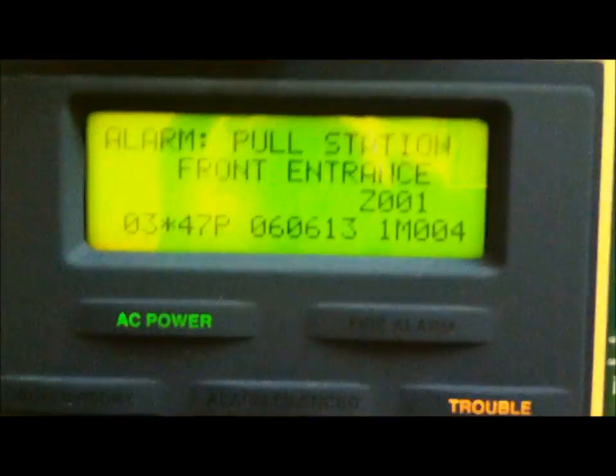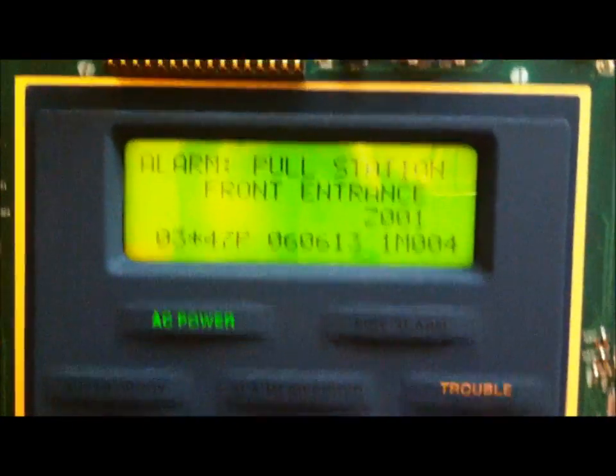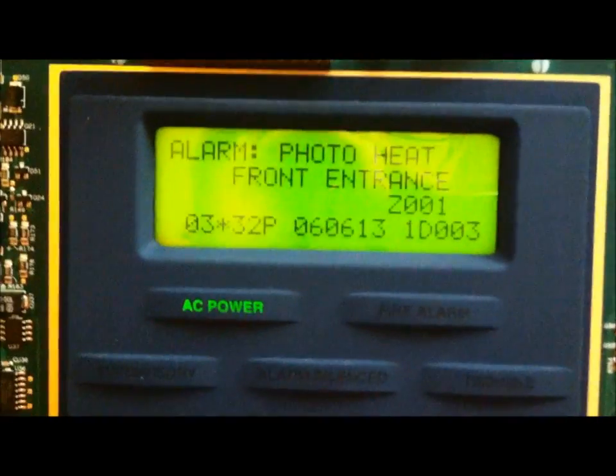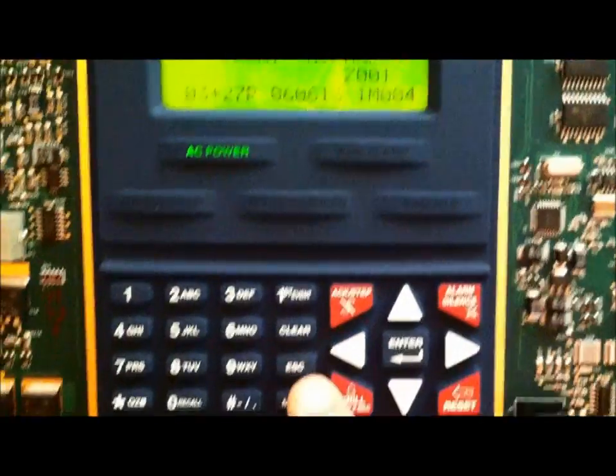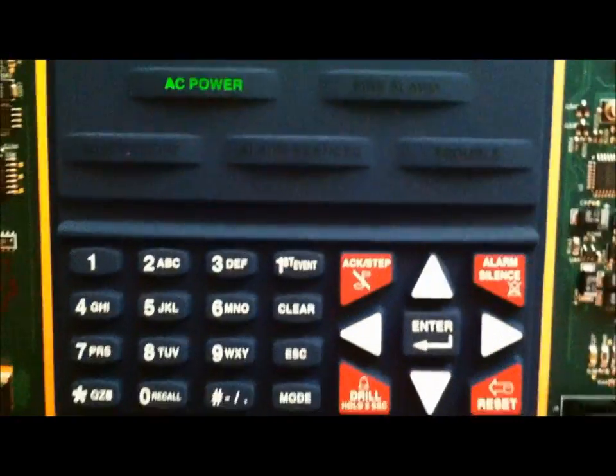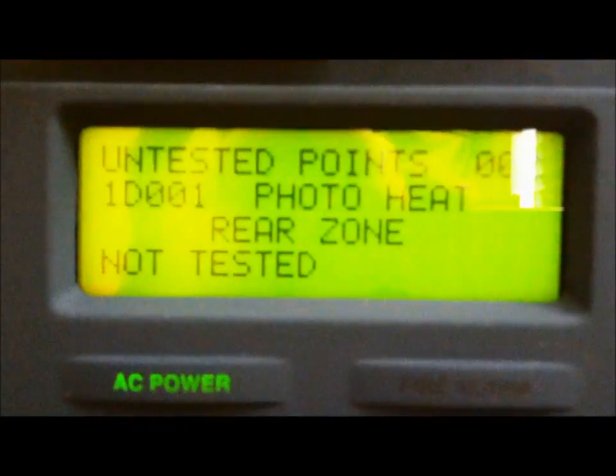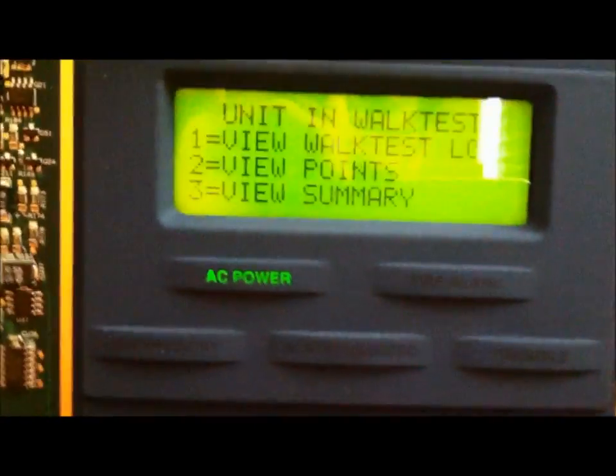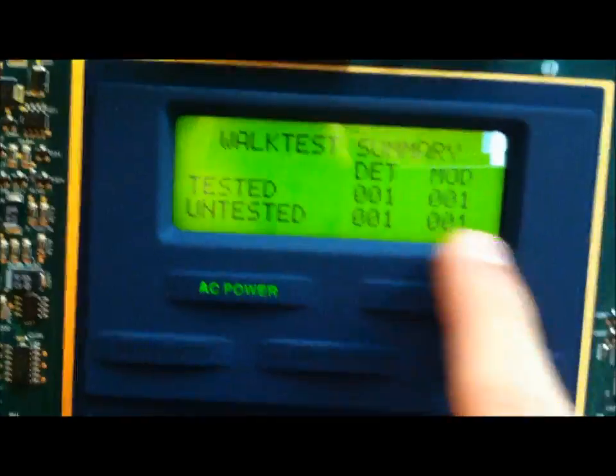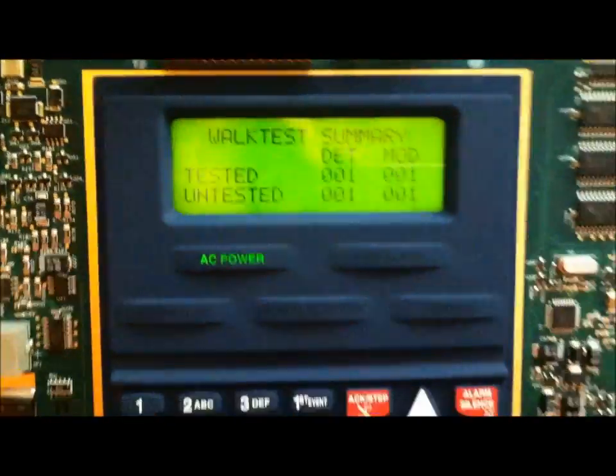I'm going to go down. There you go. Front entrance, smoke detector. There should be two untested points, the pull station and smoke detector in the rear zone. Smoke detector, pull station. Those are the two untested points.